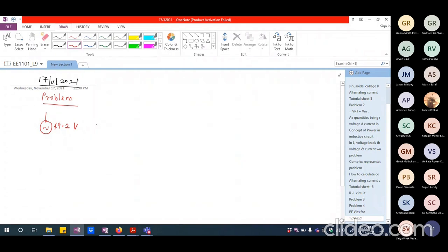If you want to know whether a device can withstand the actual peak voltage, you multiply the RMS value by √2. For India's 230 V RMS, that gives 230 × √2 = 325 volts peak. The single-phase voltage range is normally 220 to 240 V, though sometimes there is sagging — it can come down to 190 or 180 V, though that's rare. Our power system is constantly improving.